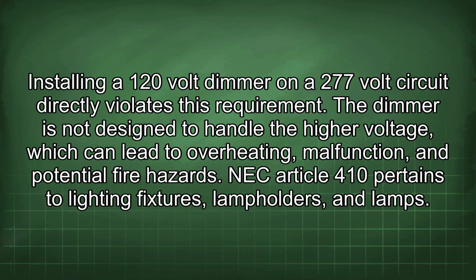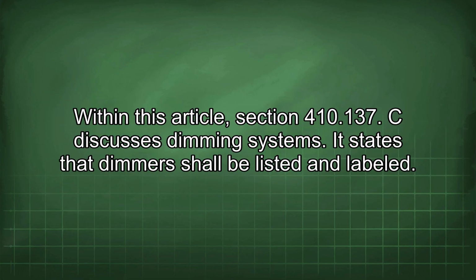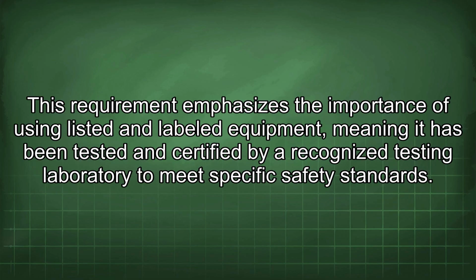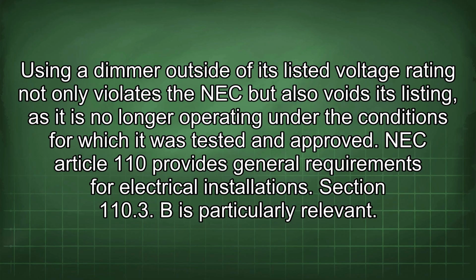NEC Article 410 pertains to lighting fixtures, lamp holders, and lamps. Within this article, Section 410.137(C) discusses dimming systems. It states that dimmers shall be listed and labeled. This requirement emphasizes the importance of using listed and labeled equipment, meaning it has been tested and certified by a recognized testing laboratory to meet specific safety standards. Using a dimmer outside of its listed voltage rating not only violates the NEC but also voids its listing, as it is no longer operating under the conditions for which it was tested and approved.